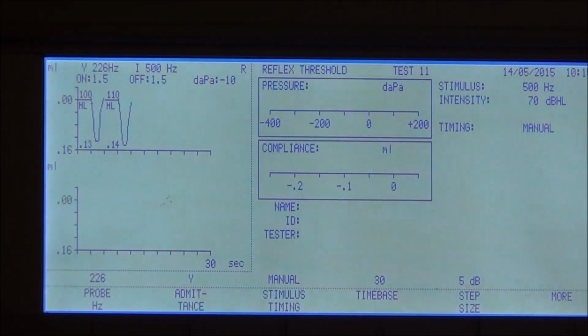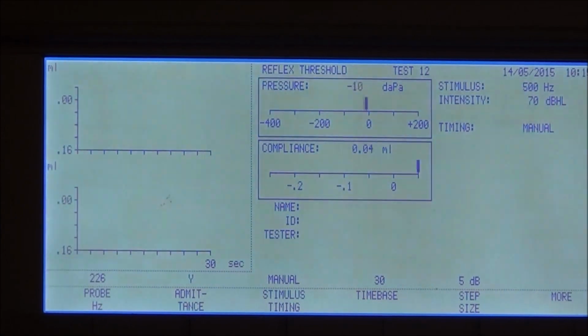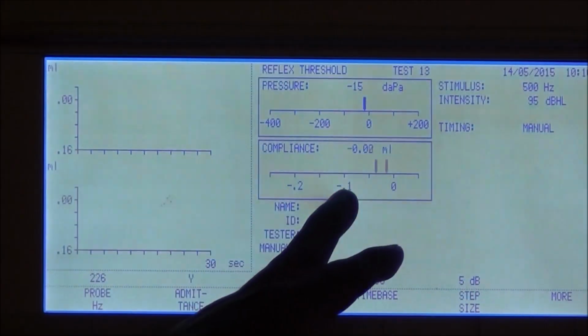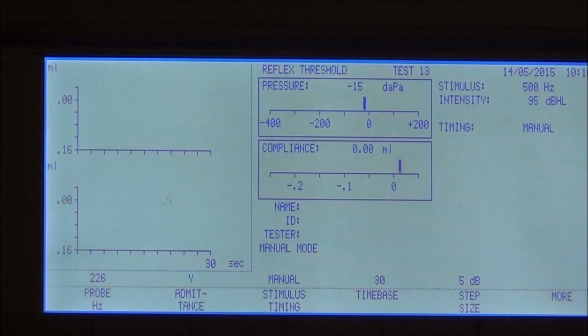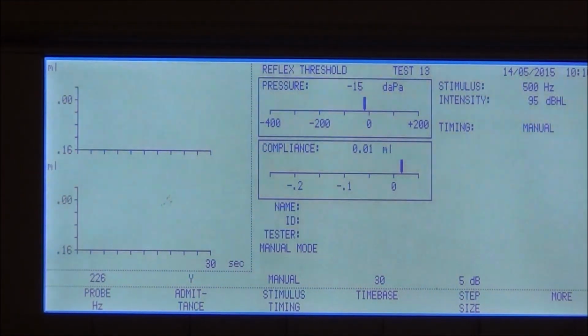So the best way to find out, if you have any doubt, is to first put it to the manual mode of stimulus timing. Press start. If you are not sure whether the reflex is present or absent, keep pressing that. Did you see this? This is the compliance with manual mode. If the compliance is close to 0, which is at the peak compliance, now when I am pressing the stimulus, you see this compliance graph showing a negative value, and it will be sustained as long as I am pressing it.